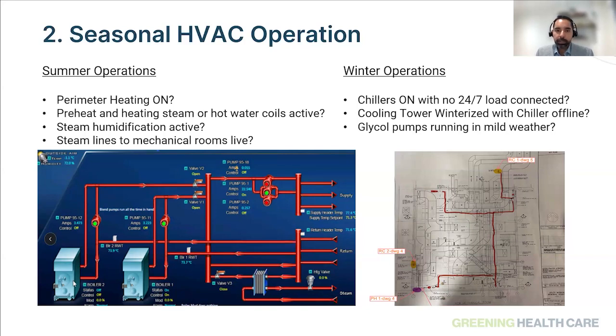So again, something you can assign to your staff is to go around and look at whether the perimeter pumps are on in the summer. In some cases, it's as easy as turning those pumps off. In other cases, there are loops that are tied to your main hot water loop, so in those cases you would have to put in isolation valves to isolate the perimeter heating from the main loops.